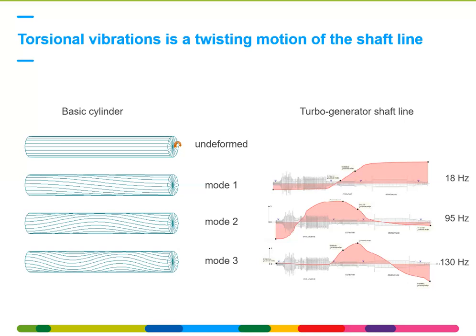If you go to the right of the slide, you can see a typical gas turbine shaft line, where you have the lowest three natural frequencies in torsional vibrations. Let's look at the first one, highlighted at 18 Hertz. This is merely an example, but it's more or less the order of magnitude, around 20 Hertz for a gas turbine shaft line. The gas turbine and the compressor rotor are twisting in anti-phase with respect to the generator, and this happens at 18 Hertz. So if something happens on the grid, you're running at the 50 or 60 Hertz speed, and superimposed on this nominal speed, you would have an 18 Hertz torsional vibration.